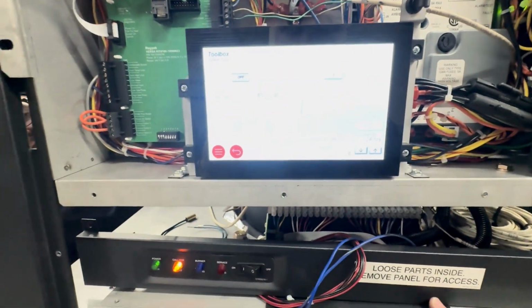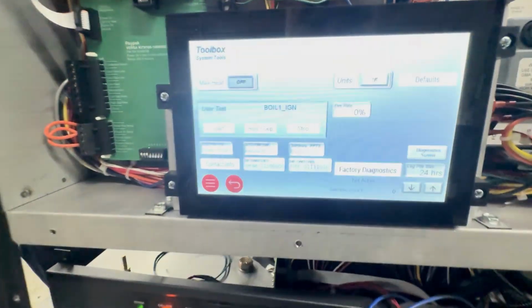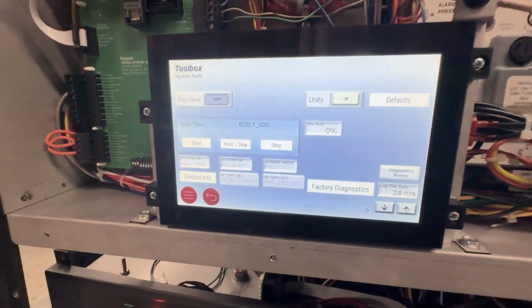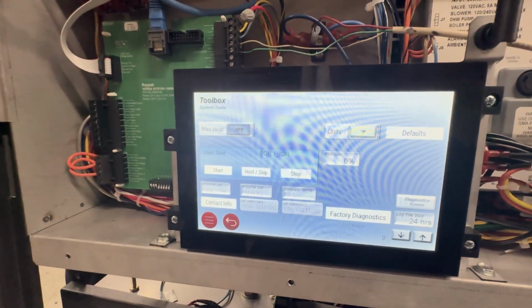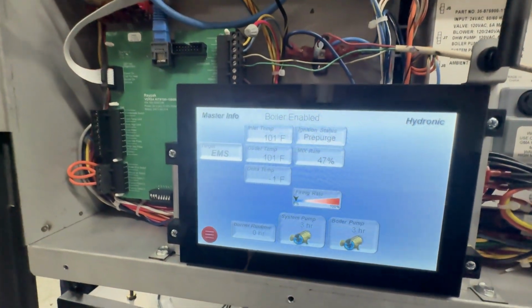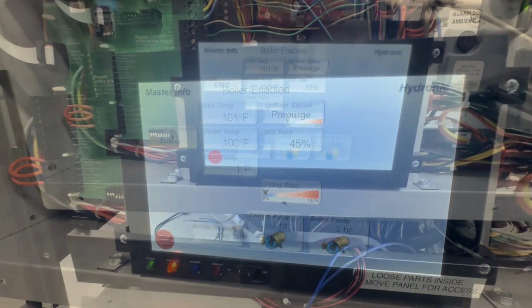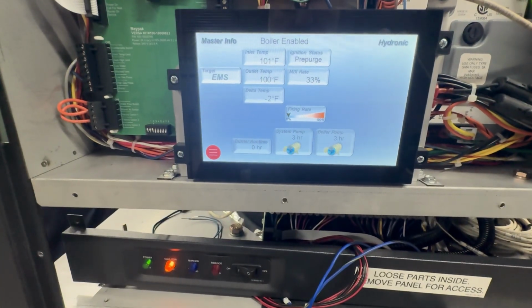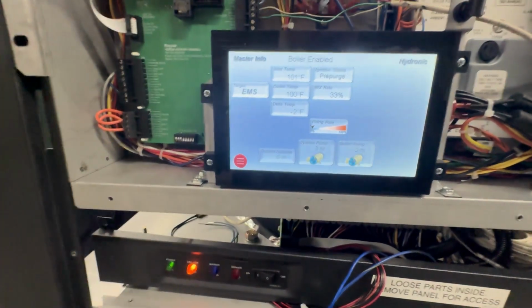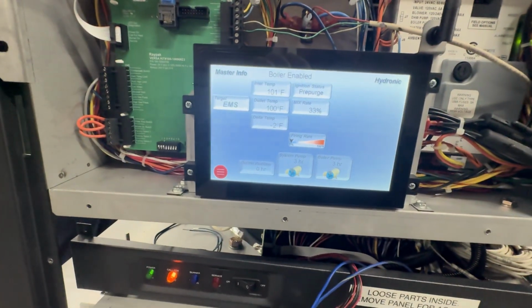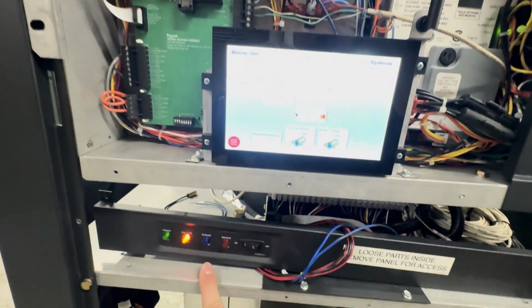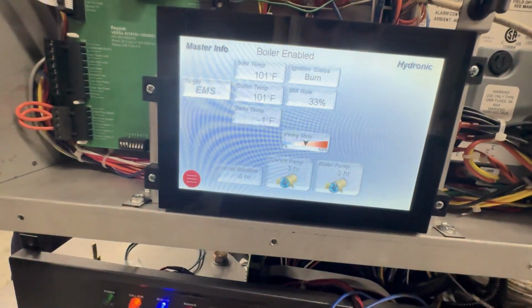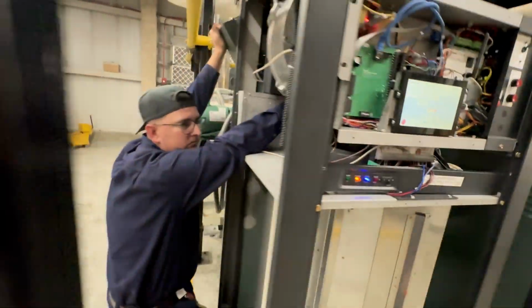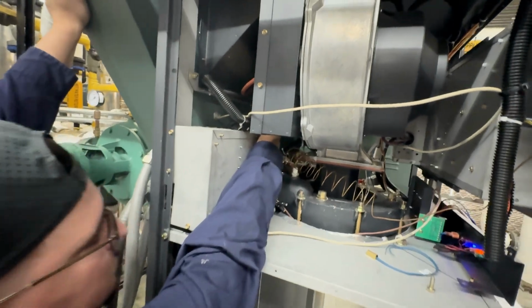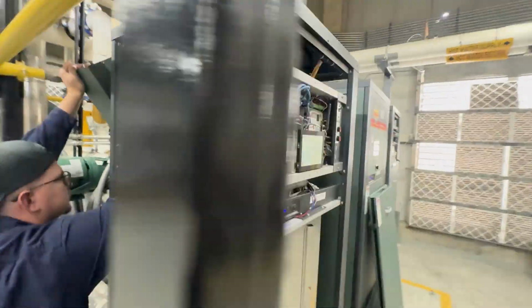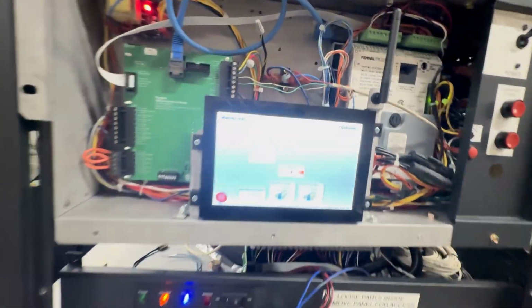We're running through user test one more time. Call for heat is on. We're waiting for the boiler to go ahead and open that gas valve and ignite. Still in pre-purge. There's the gas valve. Wait for the flame to prove. Flame's proved, ignition's on burn. Tyler over here is gonna slowly isolate that ball valve. We're gonna monitor to make sure that the boiler shuts off on low gas pressure.